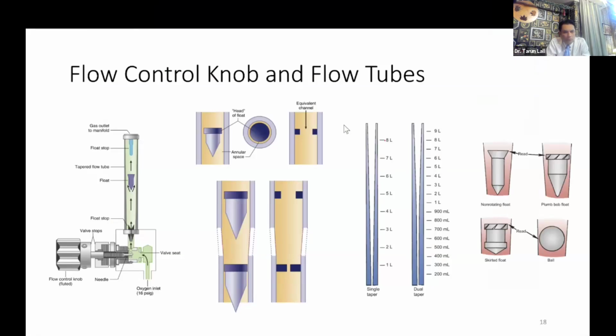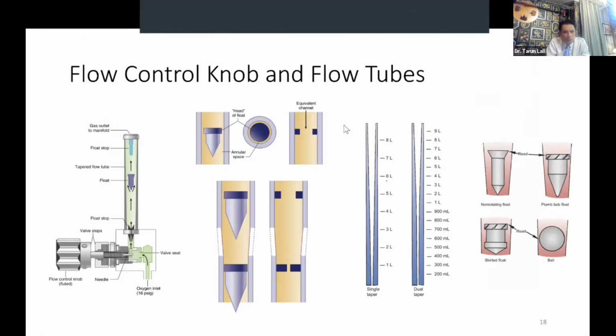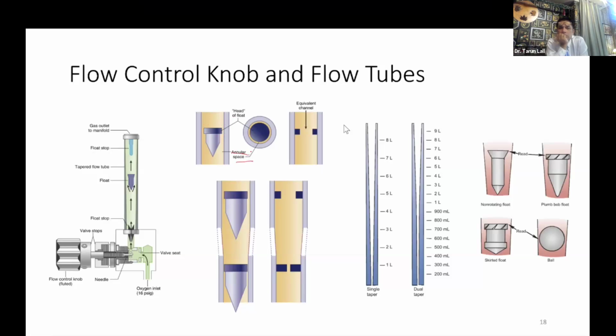As I covered in the history part also, this vertical tapering tube is what is known as the Thorpe's tube. If we look at it in cross section, you can see that around the bobbin is the annular space. The size of the annular space determines how much flow is going. These tubes are precisely calibrated for a gas. In the olden machines, sometimes there would be a temptation: I have lost one bobbin, so can I use the bobbin from the adjacent tube for oxygen? No, the bobbin, the tube, everything is calibrated for the particular gas that it is to be used for, and therefore these are not interchangeable. It should be used only from that precise manufacturer, because it is meant for that particular tube only.